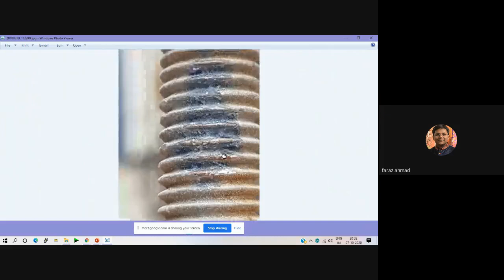Yes sir, these threads have been disfigured by electrical sparks just because the bolt was not tight enough. By tight enough I mean it has to be done with very large forces, so that it doesn't loosen up because of temperature variation. The thing I talked about temperature variation regarding the dam also applies to all the other metallic structures. This was the bolt that was holding the cable.